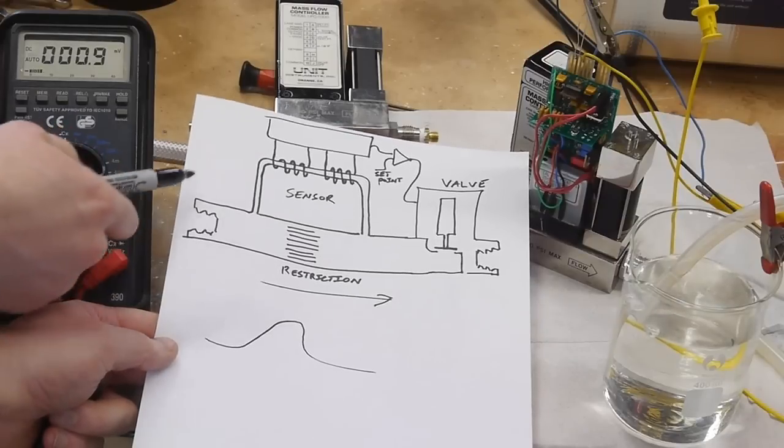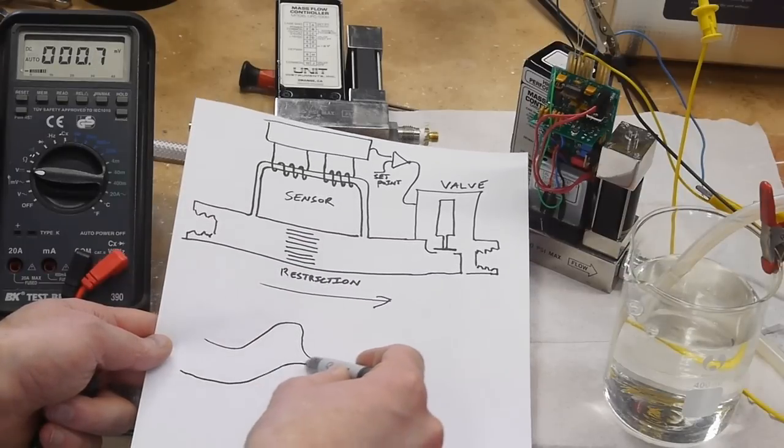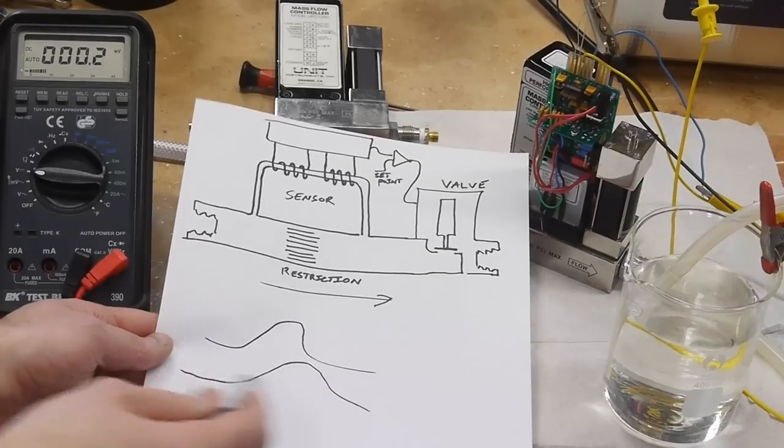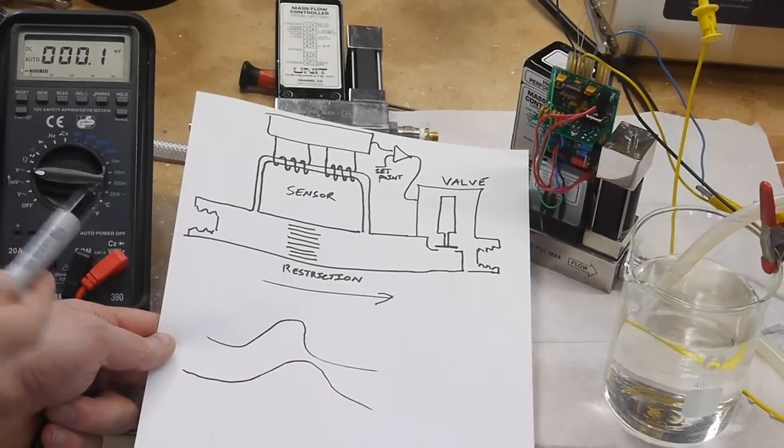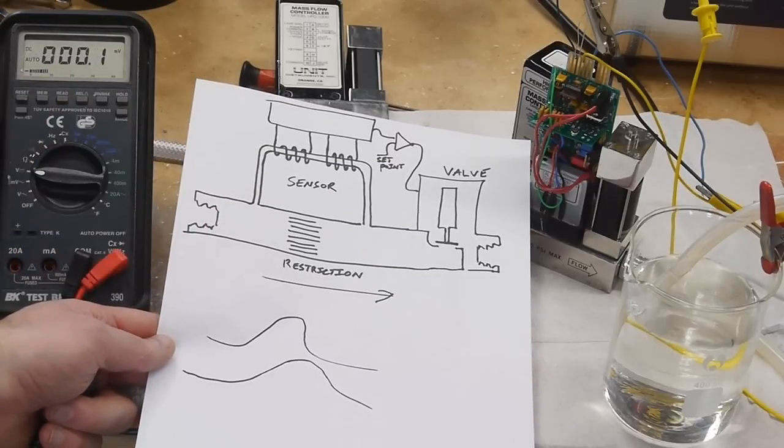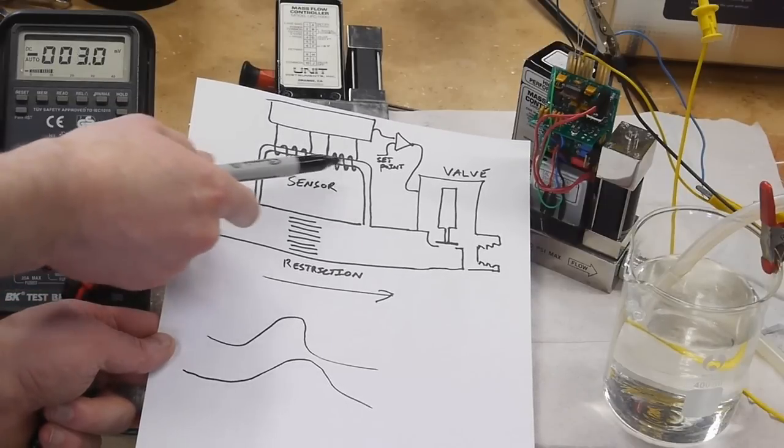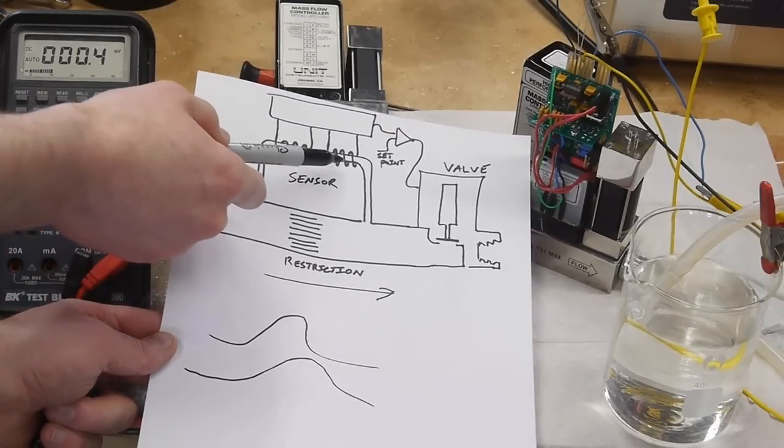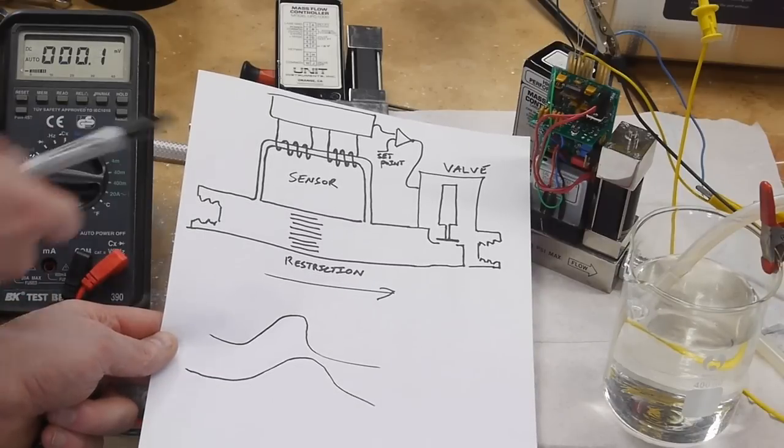However if there's gas flowing through this little sensing tube the profile will look something more like this, it will be shifted over and it will be spread out, it will be a little bit more lopsided. So basically we've got two wound coils around the sensing tube and if there's gas flowing through there the further down part of the tube will be hotter. In other words this coil will be hotter because the temperature profile has shifted over and we can sense that difference with the analog circuitry so we know that there's gas flowing through there.